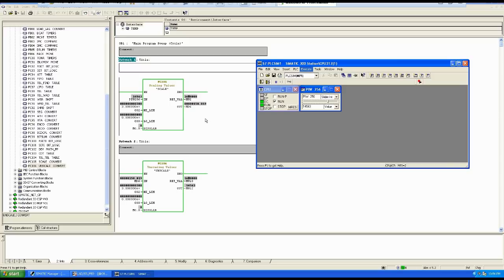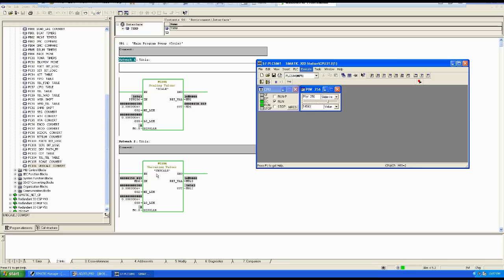The unscaling function is the inverse of the scaling function. In the scaling function you take a raw value as input and get an engineering value as output. In the unscaling function you take an engineering value as input and get a raw value as output. So FC105 is used as the scaling function and FC106 is used as the unscaling function. You can see the raw value here as input and the output is 158-point-something as the engineering value, and then that engineering value becomes the input to FC106 and the output is the raw value again.